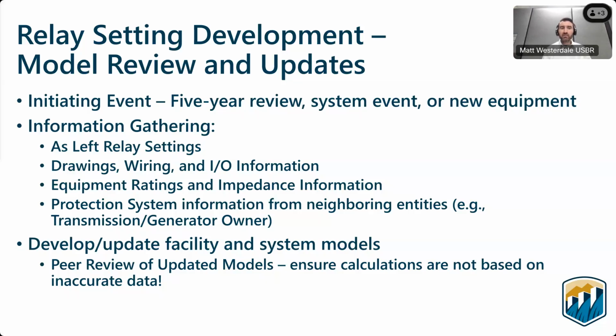Another initiating event that might necessitate a need to look at relay settings would be some sort of system event that occurs out on the bulk electric system. So if things didn't operate appropriately or operated differently than expected, it may require a review. Additionally, if you have any sort of new power equipment or new relays, that might need to generate some sort of review work or evaluating the coordination of relays.